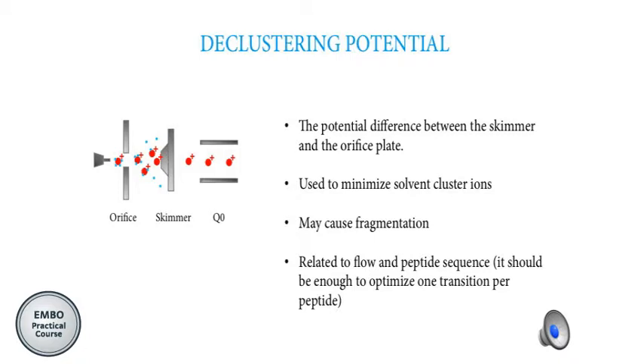The declustering potential is used to minimize the cluster ions that are formed between the analyte and the solvent. You need to be careful because a very high declustering potential can cause fragmentation of the analyte. This is related to the LC flow and to the peptide sequence, so if you want to optimize it, it is enough to optimize for one transition per peptide because the optimal value will be the same for all transitions.